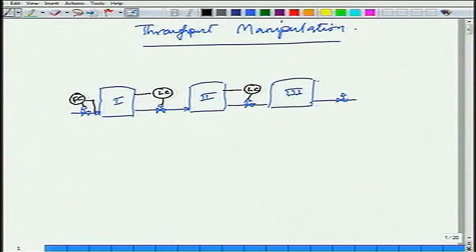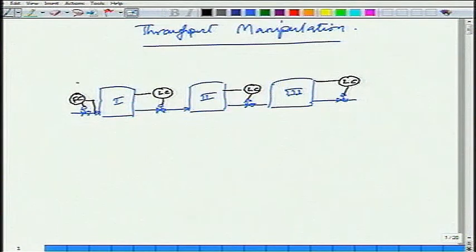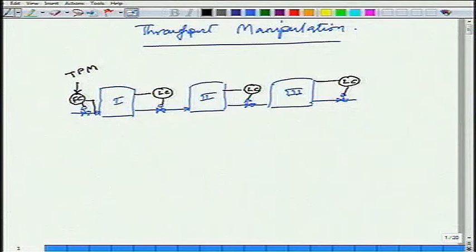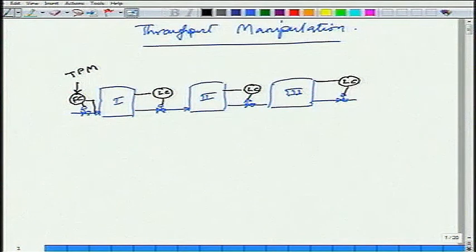The flow through the train is downstream and the level controllers are also oriented downstream. If you want to increase or decrease your throughput, this is the set point which your operator would adjust — the TPM, throughput manipulator. So the set point used to increase or decrease production is called the throughput manipulator. The throughput manipulator is like your gas pedal in the car — that is what you use to increase or decrease production. For this control system, the throughput manipulator is the feed to the unit.